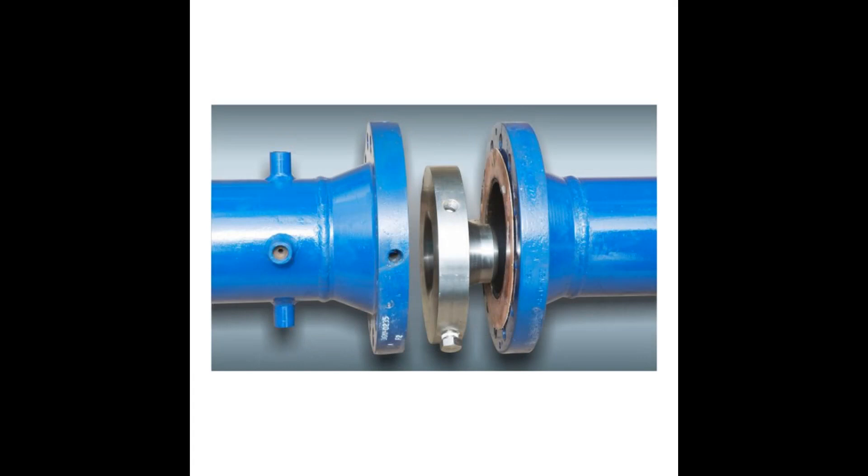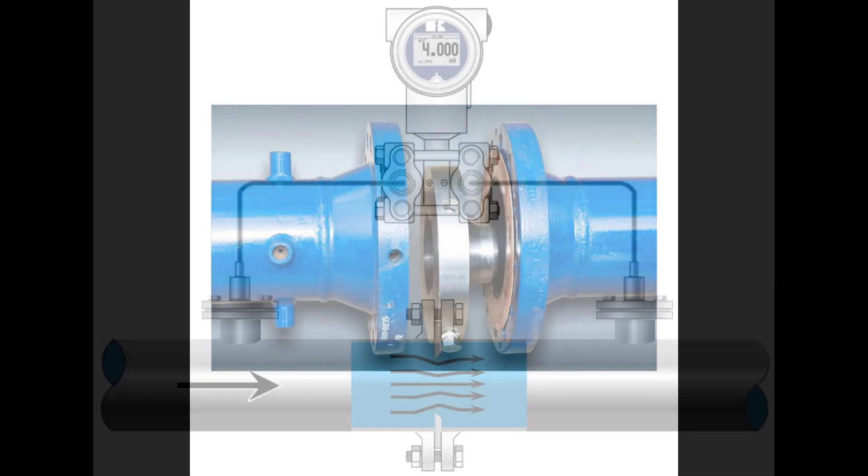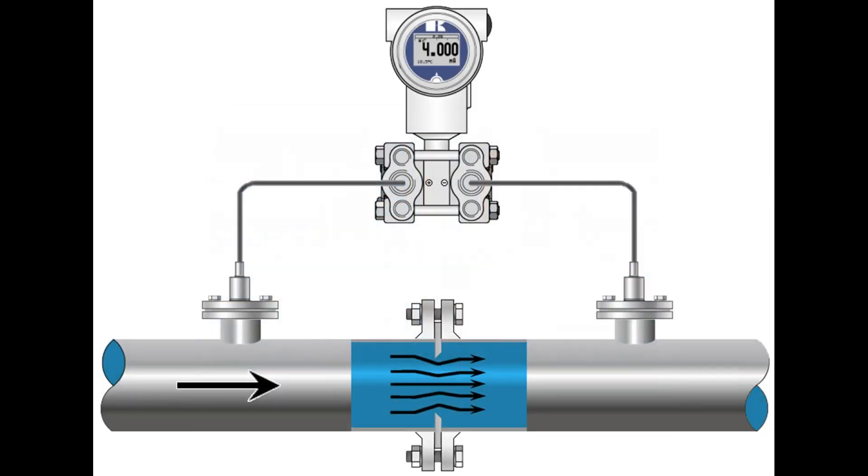Here's a detailed explanation on how a differential pressure transmitter measures flow. The primary element is installed in the pipeline, causing a restriction in the flow. As the fluid flows through the restriction, its velocity increases, resulting in a pressure drop across the primary element.